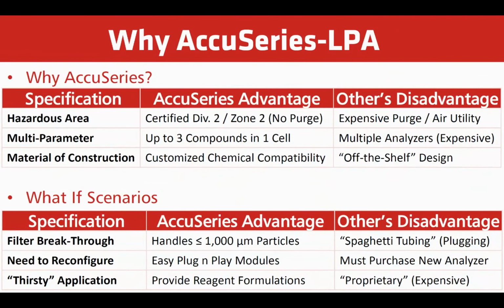So why AccuSeries? Well, we offer this hazardous area certified Div 2 or Zone 2 without purge. So there is no plumbing necessary for instrument air, and there's no purge to go bad. It just simply meets this without any purge. Multi-parameter, again, up to 3 compounds in one sample or one analyzer, one cell, so it eliminates the need for multiple analyzers.